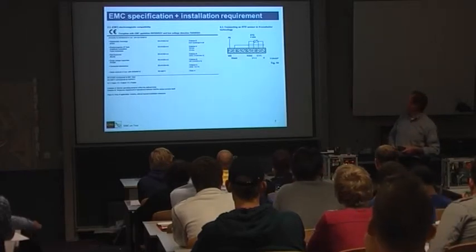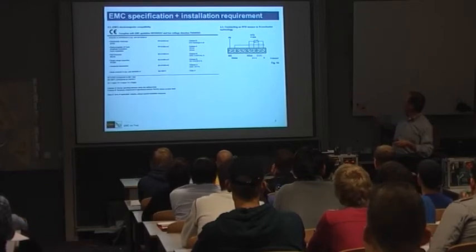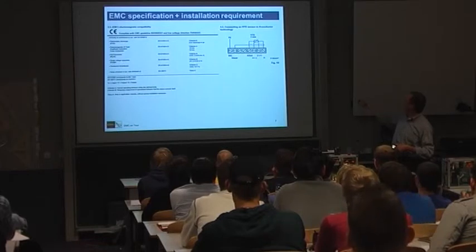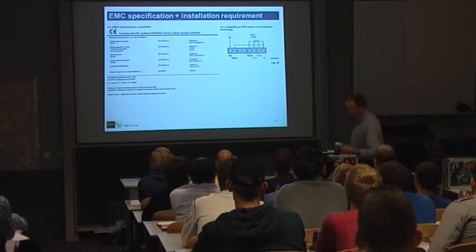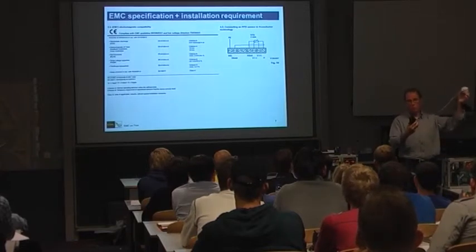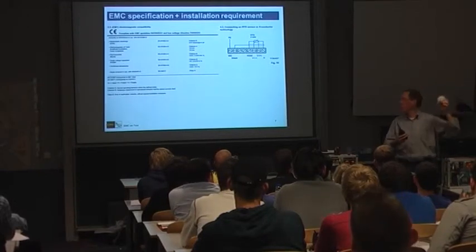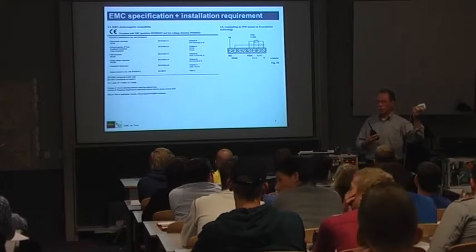And there's another thing: if I look at page, let's say page 70, somewhere in the back of the manual, I can see that I have to use a screen for the sensor. Whereas I didn't read the manual, I just used a plastic lamp and unshielded cable. That's probably the big difference. So there are two issues: the specification of the device and the cabling, the quality of the cable.